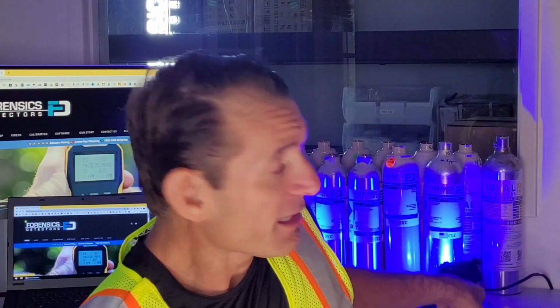Make sure you bump test before using, before your day's operation of your monitors, folks. Bump test on a very regular basis to make sure your equipment is working. The previous person may have dropped it, may have done something precarious that renders the gas detector inoperable. You do not know. That's why bump testing is very important before undertaking a very important sample. Or I recommend bump test daily.